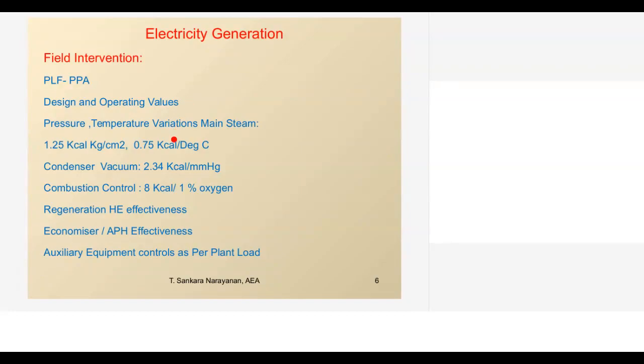So here certain heat rate variation is given. Pressure can vary, temperature of the main steam can vary. So between the boiler and the turbine floor itself, there can be a difference in temperature. And sometimes, due to fuel quality, we may not get pressure nearer to the design pressure. So these figures are given for a 210 megawatt plant. If the pressure is reduced by 1 kg per centimeter square, heat rate will change by 1.25 kcal. Similarly, the temperature variation is there; the kilocalorie variation is around 0.75. So for this one we can refer to the Mollier chart and get what the normal variation will be when there is a change in pressure and temperature. Predominantly, pressure plays the major role.